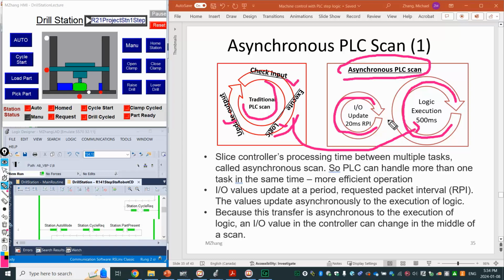That causes some problems, because your logic may run, for example, 500 milliseconds as one cycle, but your I/O update maybe 20 milliseconds at a time. They call this the RPI, the request packet interval - you can search this term.